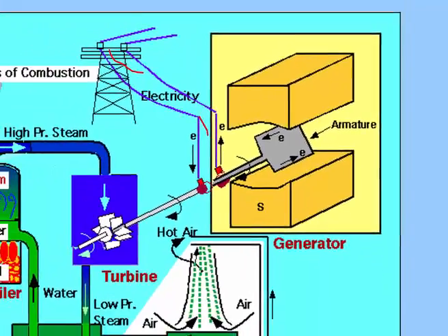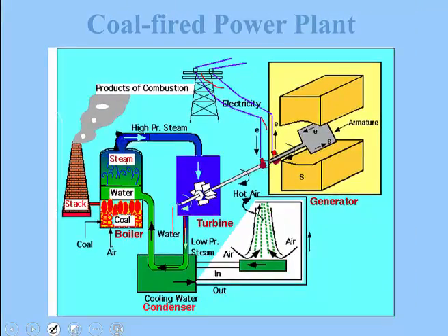And the low pressure steam that is coming from the turbine is condensed in a condenser. And the condensing water, which goes in, becomes warm and comes out and goes to a very high height, and then it is sprayed in a cooling tower, and the energy is transferred to air, and the water comes down and is recycled. So those are the details here.